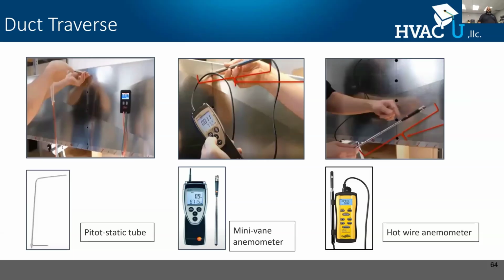We also have a duct traverse. We used to do this quite often before we started using flow plates. The duct traverse, we're going to drill test ports inside of a duct system, maybe a supply or return, and we're going to use a hot wire or pitot static tube, and we're going to basically take velocity measurements in the duct, right? If we take velocity measurements in the duct based off this traverse, we can take the average velocity of the entire traverse we do, multiply that by the area of the duct, and we can calculate CFM. Really accurate, however, it was pretty time consuming. You still see this as a required step in commercial test and balancing, but with flow plates becoming more popular, you see this maybe not as quick as a solution, but it's definitely still accurate and something you should consider.